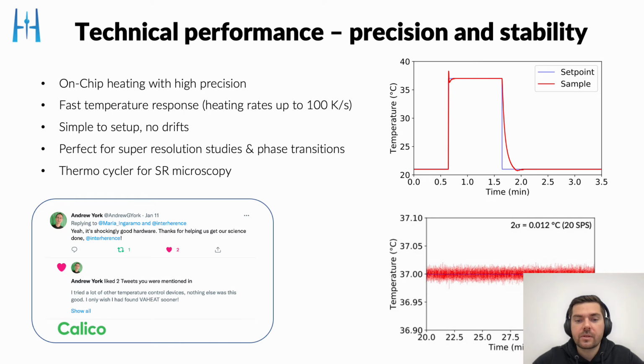The technical performance of the system was quite important to us. On the one side, it's very precise, so you can stabilize the temperature to a very high degree. As you see here, it's a time trace where the temperature stabilized to 37 degrees C, and we achieve a standard deviation below 0.01 degrees C over an extended period of time. So in principle, the system, due to its fast thermal response, is similar to a thermocycler for super resolution microscopy.